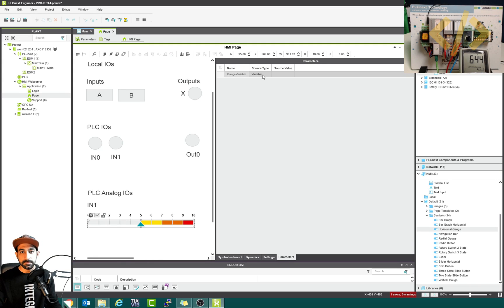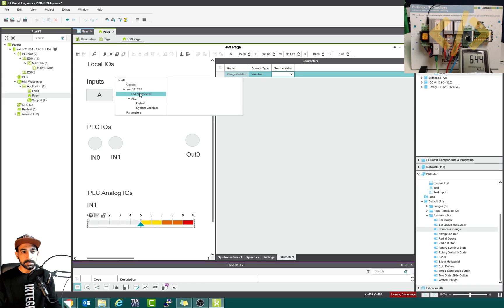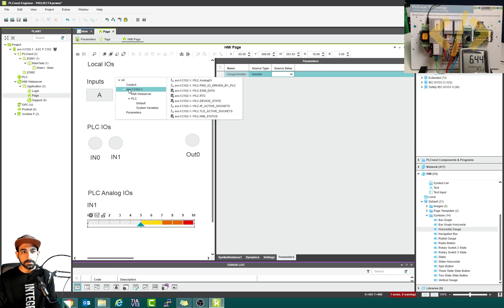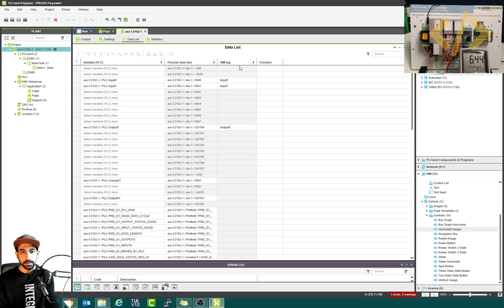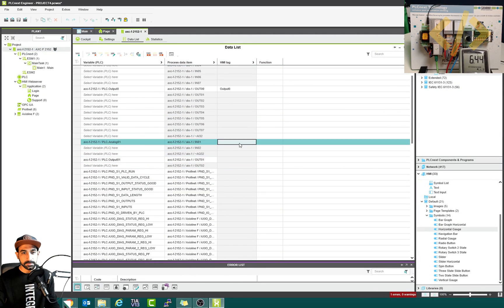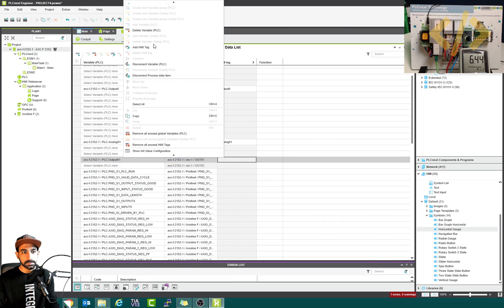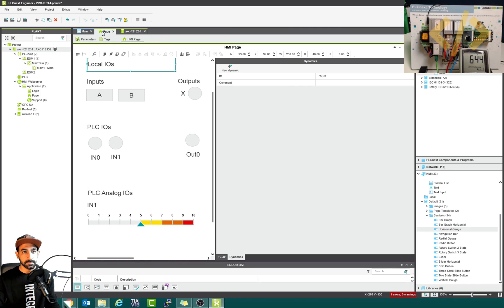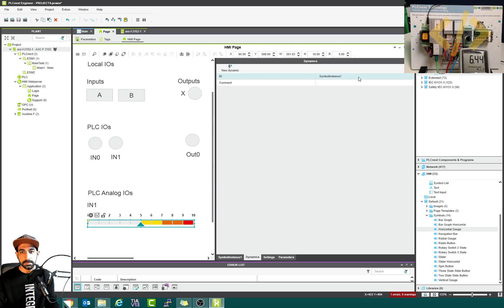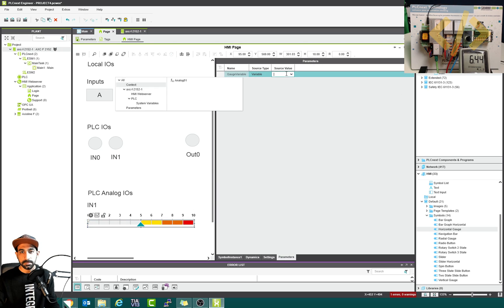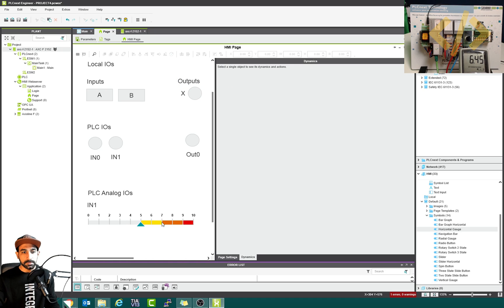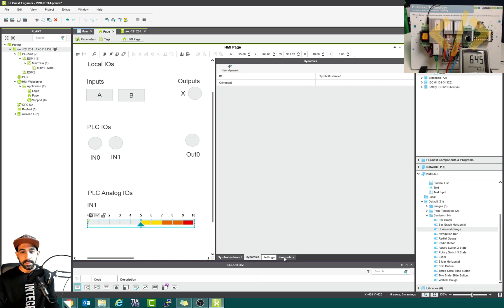Go to parameters, then variable, and define which variable you want to see. You can go to AXC and analog 01 to read directly from the PLC. But I prefer to use HMI tags — right-click here and add HMI tag analog 01, and also add HMI tag output 01. So I will read analog 01. Go back to parameters and HMI web server — now I have analog 01. This is now going to read my analog input 01.